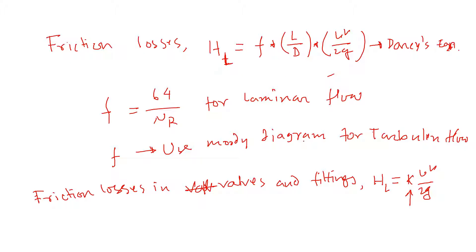If you compare these losses with Darcy's equation, we can write k times v squared over 2g equals f times equivalent length. That indicates, instead of just length, you're trying to find how much length loss in a straight pipe is equivalent to a certain fitting, like for example an elbow. So we calculate the equivalent loss in a straight pipe compared to an elbow.